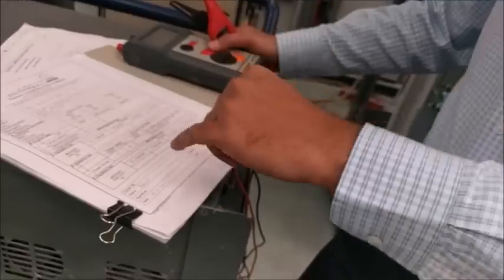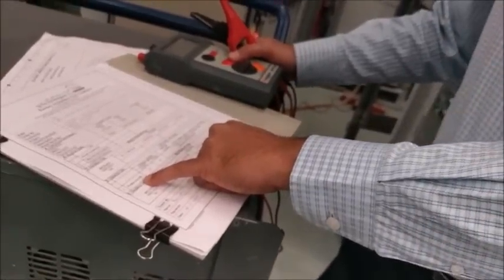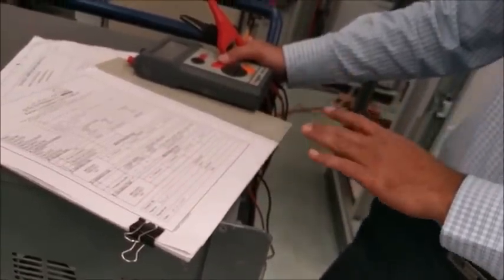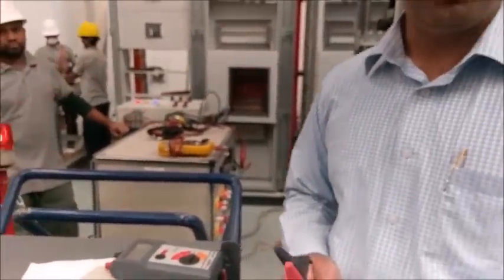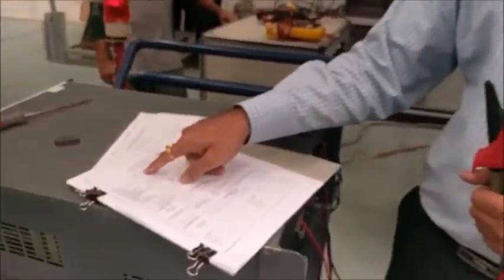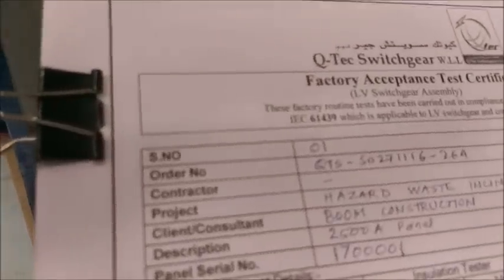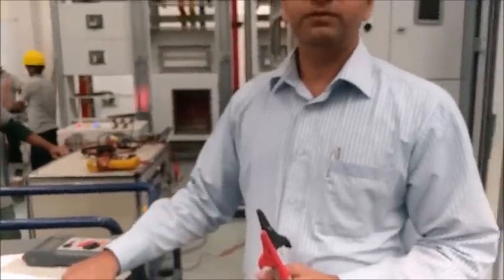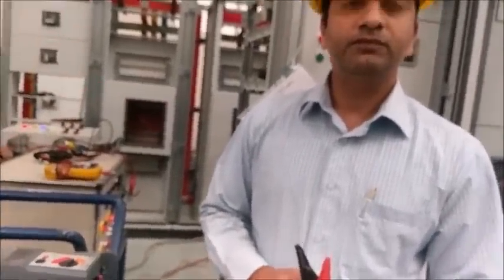So this is the test for dielectric performance. After that, this is an HV test, high voltage test. In the high voltage test, this is a kit. We have to apply 2.5 kV, means 2500 volts, for 1 minute. This is according to IEC 61439, for 1 minute, for the total panel, all components.